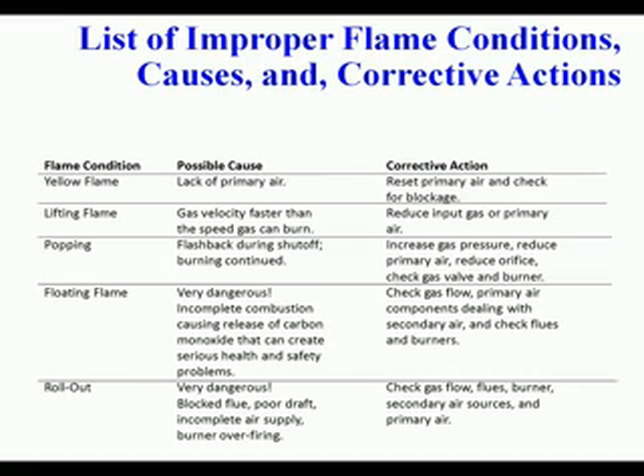If you have a yellow flame, it's a lack of primary air. To fix it, reset primary air or check for blockage. Lifting flames: the gas velocity is faster than the speed the gas can burn. Reduce the input gas or primary air. Popping noises are flashback during shutoff and burning continued. Increase gas pressure, reduce primary air, reduce orifice, check gas valve and burner.